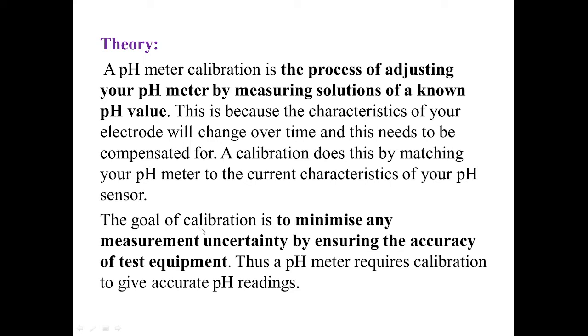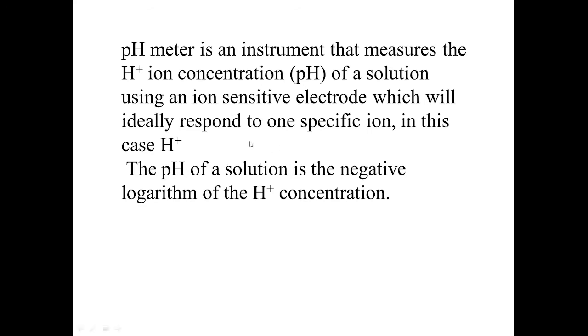So what is the basic goal of a calibration? It is to minimize any uncertainty in the measurement by ensuring the accuracy of the test equipment. That means your instrument should exactly measure the pH and give you a correct and accurate measurement. So to ensure the accuracy of the equipment, we need to calibrate it. A pH meter thus needs calibration to give an accurate pH reading. That is the main aim of calibration. And calibration is a process where you adjust your pH meter with the help of a solution having known pH value.